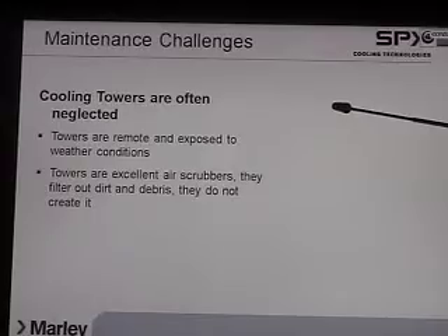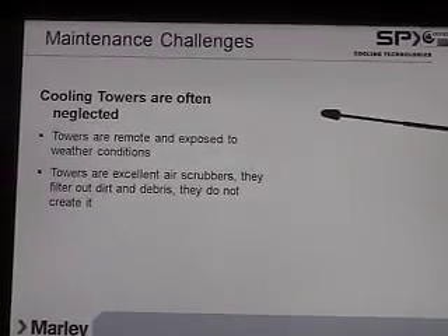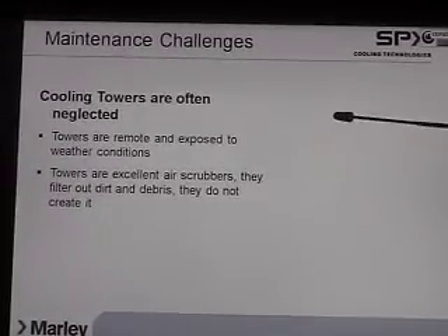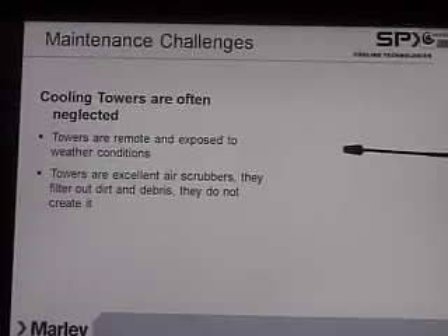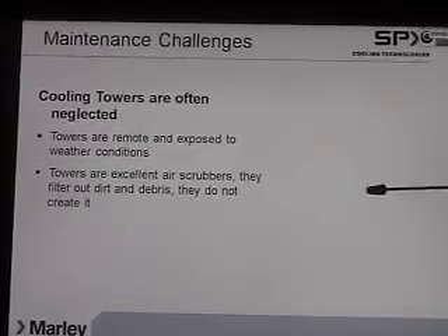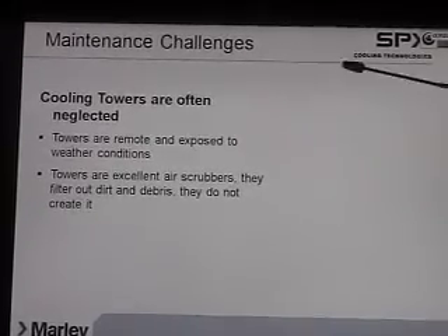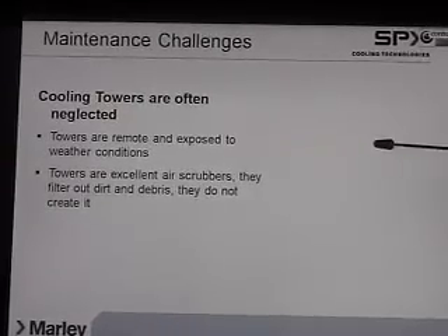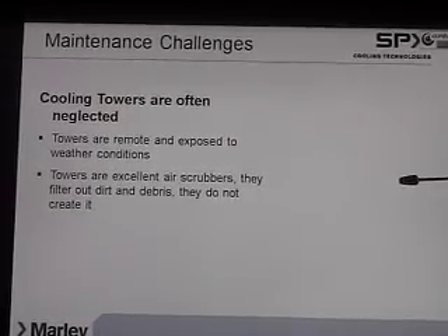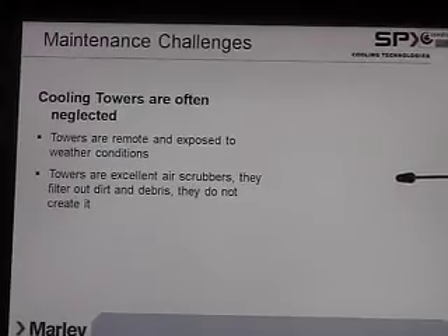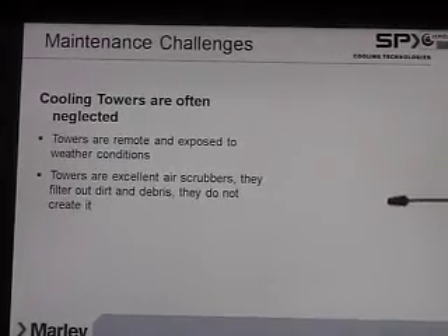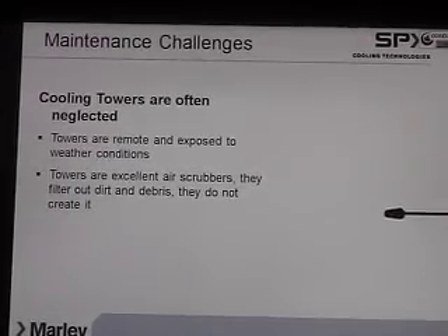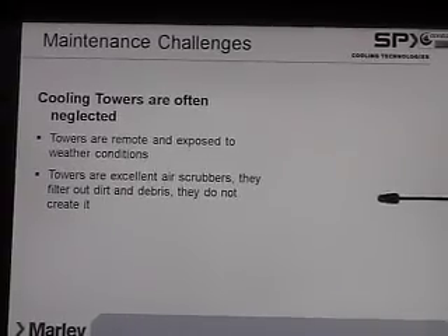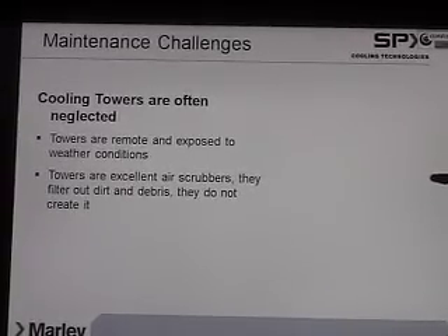The cooling towers are often just turned on and forgotten about, but there is some maintenance that is required to help your cooling towers last longer. They're excellent air scrubbers. They collect, as you know, all the dirt from the air, and it ends up in your cold water basin. But they don't create the dirt, they just filter it out of the air.